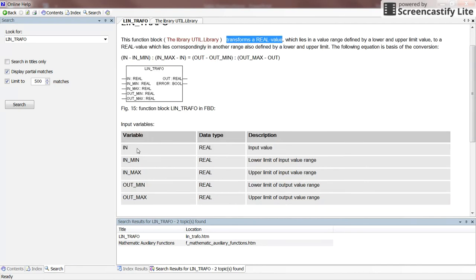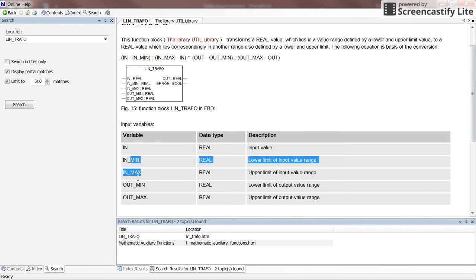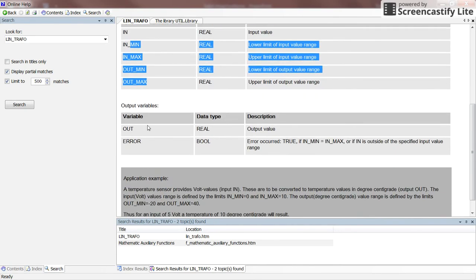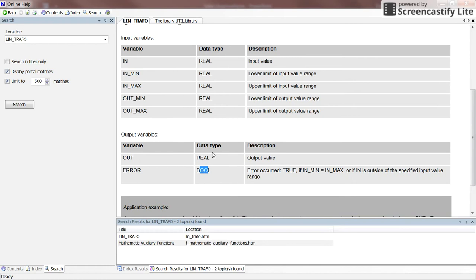In general, it has five inputs: the first is the input variable, and the next four are the parameters. It has two outputs: the first is the output variable, and the second is called error — a boolean variable that is false when there is no error and becomes true when there is an error. An error occurs if the minimum and maximum values for the input are the same, or if the input lies outside the provided range — either smaller than the minimum or bigger than the maximum input.